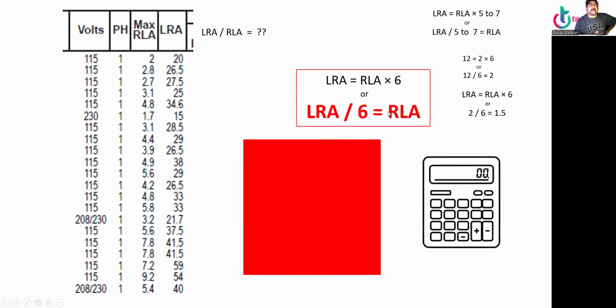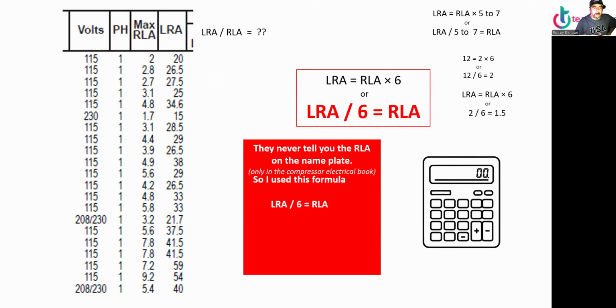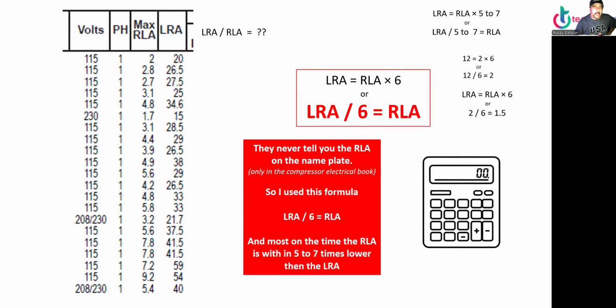Now, I did the calculation for fun to see what's going on. So long story short, I just divided the locked rotor amp by 6 so I can get the rated load amp and make it easy to see if it works. They never tell you the rated load amp on the nameplate. Only the compressor book has it. So I use the formula, and most of the time the RLA is 5 to 7 times lower than the locked rotor amp.